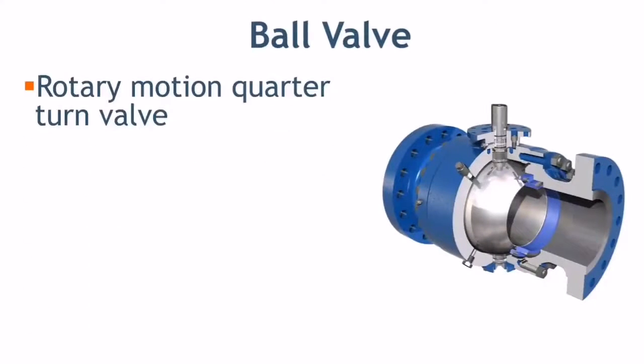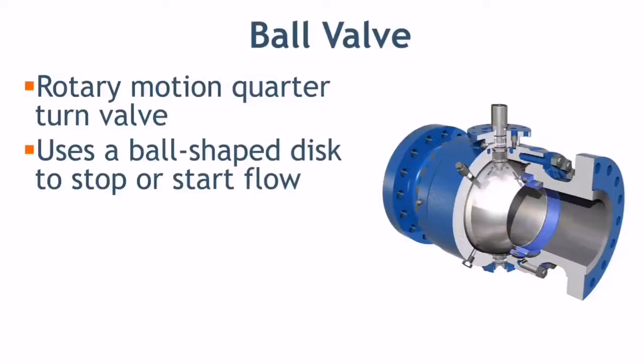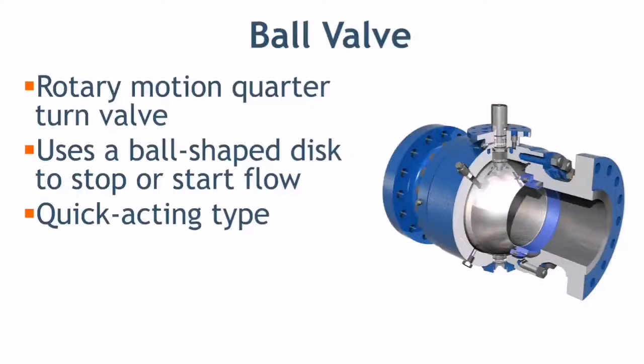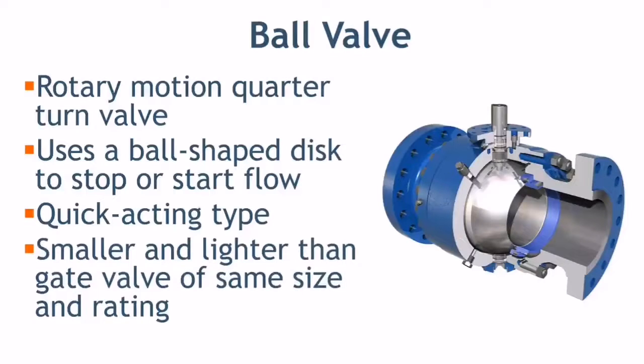Ball valve is a quarter-turn rotary motion valve that uses a ball-shaped disk to stop or start the flow. Most ball valves are of the quick-acting type which require a 90-degree turn of the valve handle to operate the valve. The ball valve is smaller and lighter than a gate valve of the same size and rating.